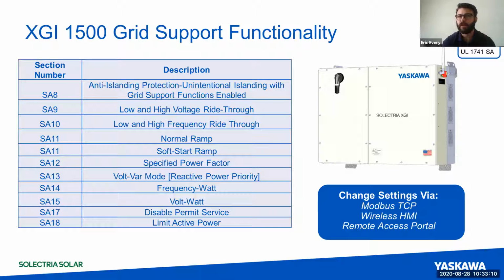This is voltage ride through and frequency ride through. So if the voltage sags or surges a little bit, instead of all the inverters tripping off at the same time, we can ride through and support the grid. Because for every kilowatt you shut off, you have to support it with a kilowatt from somewhere else. At every given moment, the load has to match the generation within a few percent. So if all the inverters turn off at the same time, you have megawatts, potentially gigawatts, of deficit that you have to make up with something else.